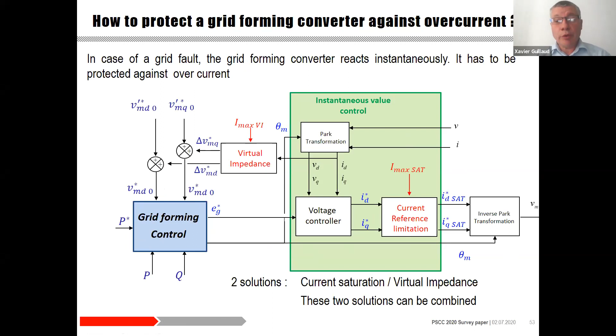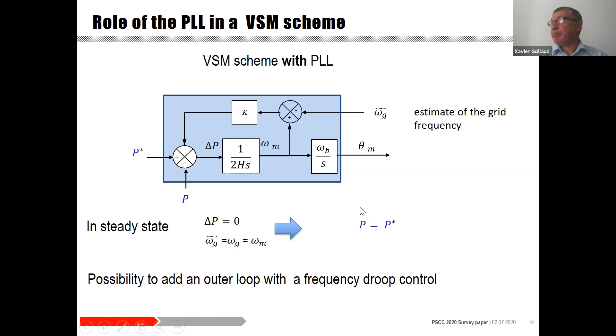Let's analyze briefly the role of the PLL in the VSM scheme. In this scheme, an estimate of the grid frequency is used. In steady state, this estimate of the grid frequency is equal to the grid frequency itself, and also omega m, which is the modulated voltage frequency, is equal to the grid frequency. Since in steady state delta P is equal to 0, it can be deduced that in steady state, the active power is equal to the reference. We have the choice to add an outer loop for a frequency droop control or not.